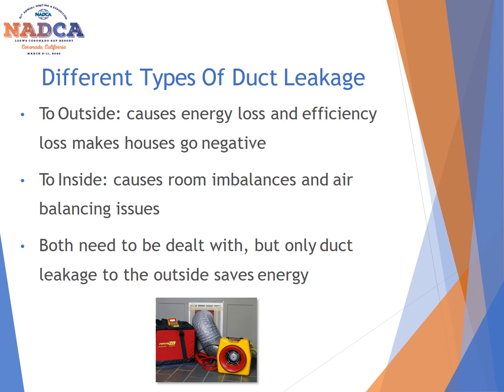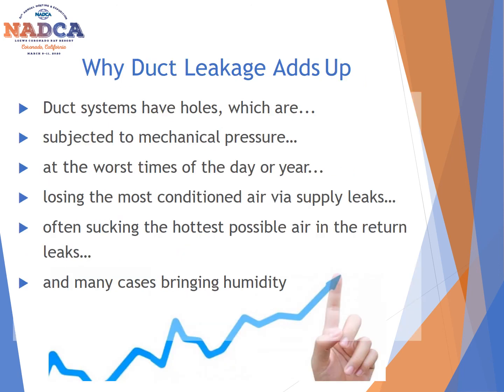The other option is if you're leaking air to the inside, it throws the balance off in the system. So you may have one area that is cooling better, but then you have another area that's not getting the air that it needs. So you need to look at both of these. It's not just a matter of how the air flows from one space to the other or the fact that it's leaking. You need to make sure the entire system is balanced in order to have a properly functioning system. Over time, duct leakage will start to add up. Duct systems that have holes in them, which are subjected to mechanical pressures, and this always happens at the worst time of the day or the year, will end up losing the most conditioned air via the supply leaks, which in turn often sucks the hottest possible air into the return leaks and may bring in additional unwanted humidity.